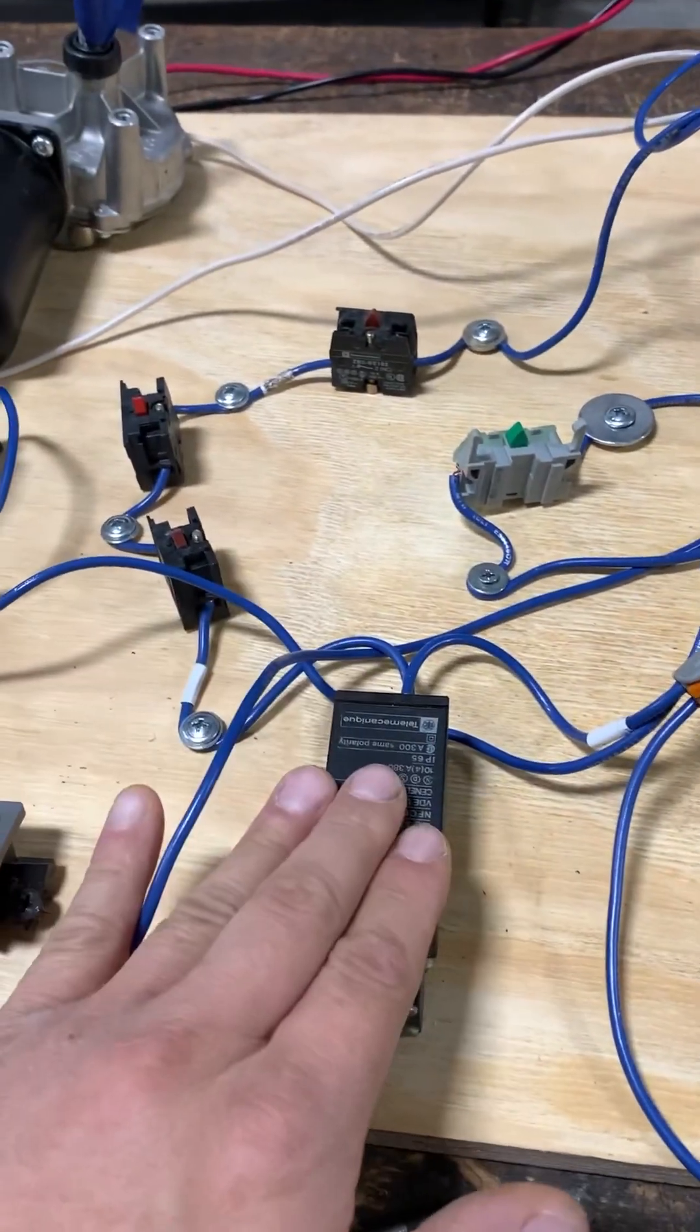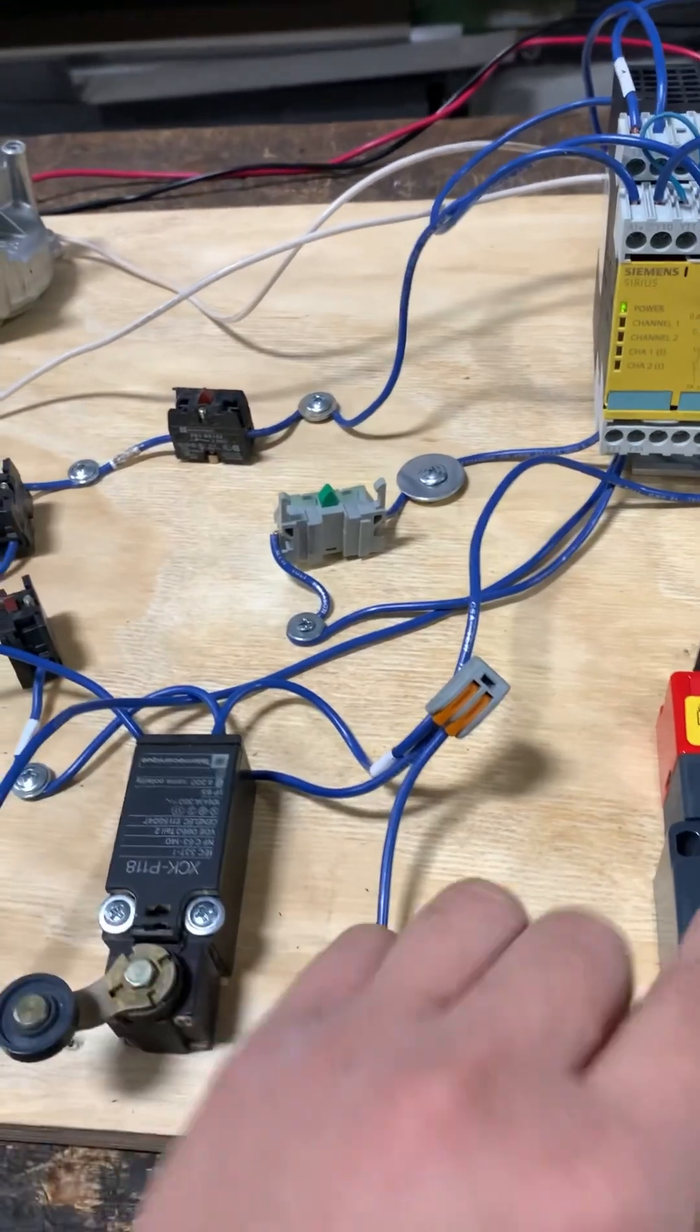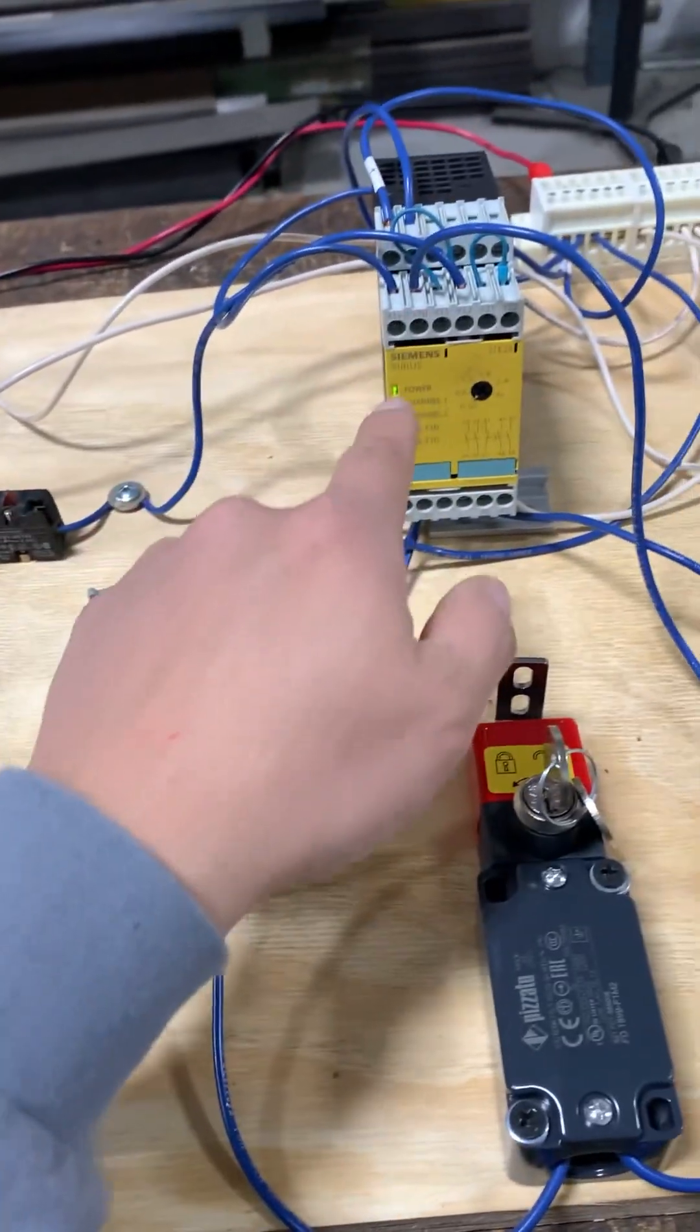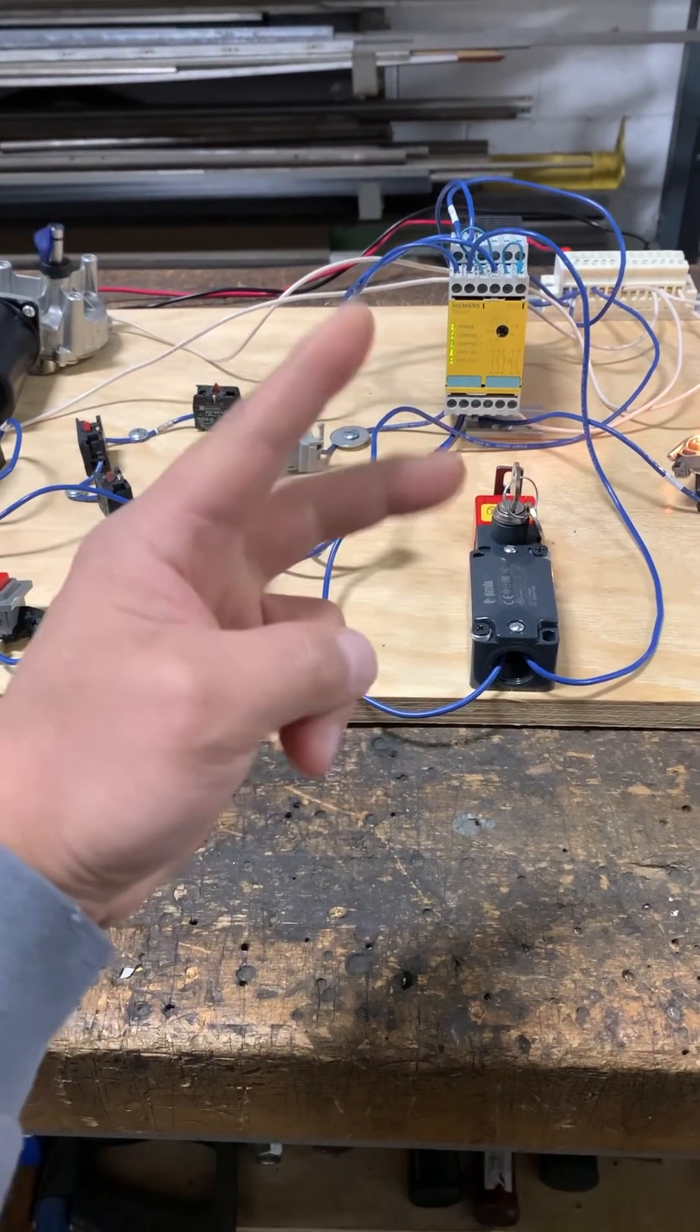Door and lock, the limit switch, the three e-stops—that's the whole safety. If any of these are open, my relay is not ready. So until next time. Deuces.